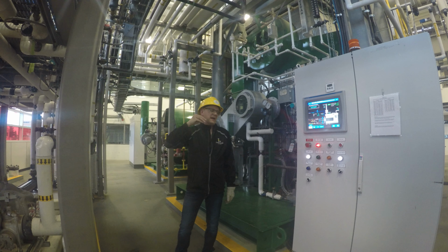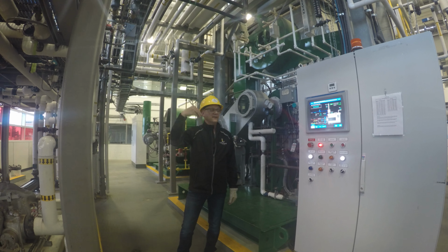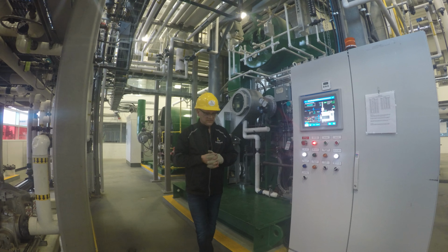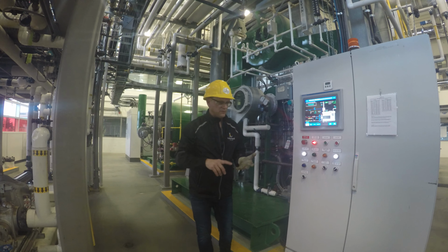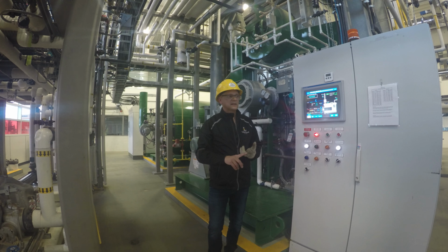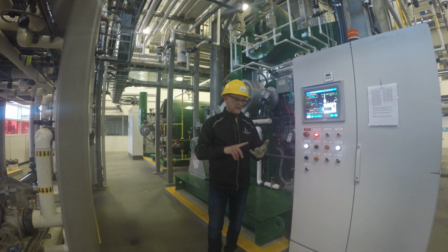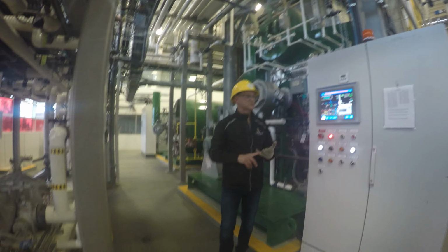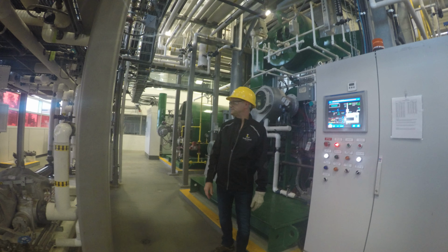It volatilizes, it becomes a gaseous state, goes with the steam, and when your steam collapses, condenses back to a condensate, then that amine works to balance the pH. We want that pH about that 8.5 to 9.5 in condensate. It's a neutralizing material, so it prevents corrosion, and it's a filming agent in there also.